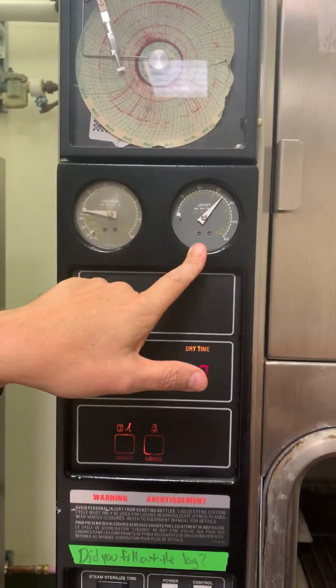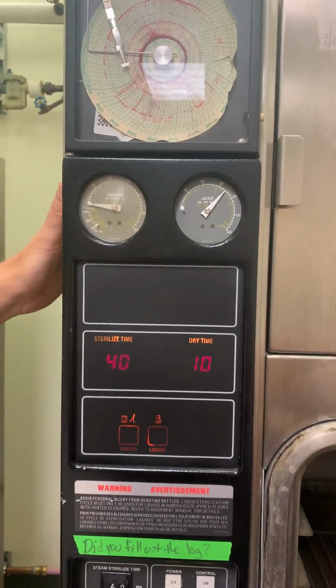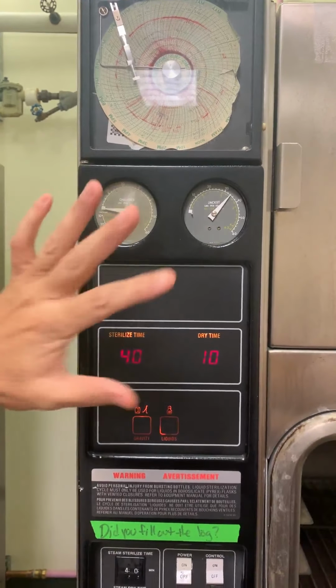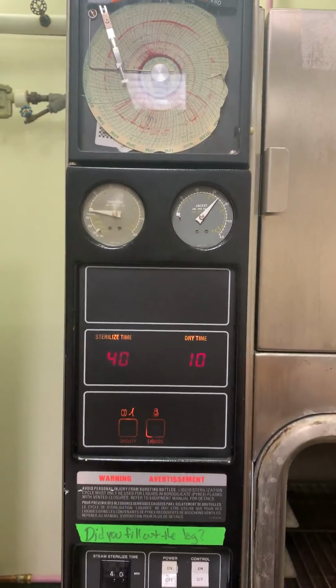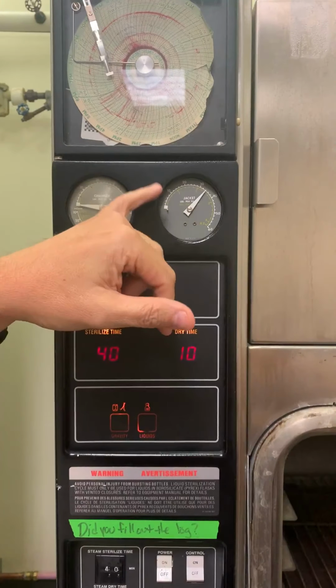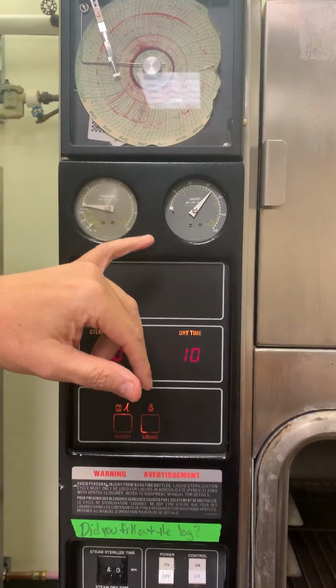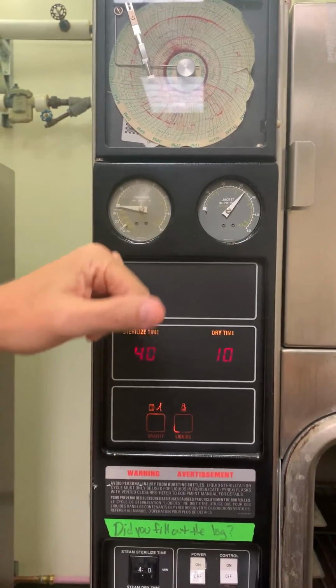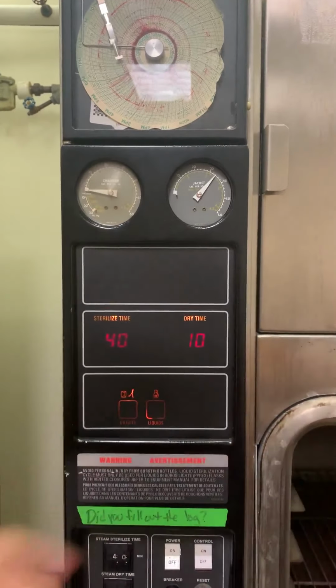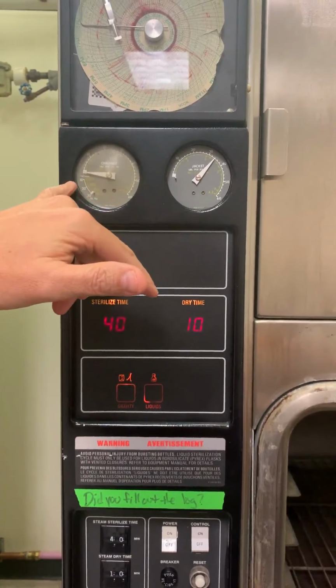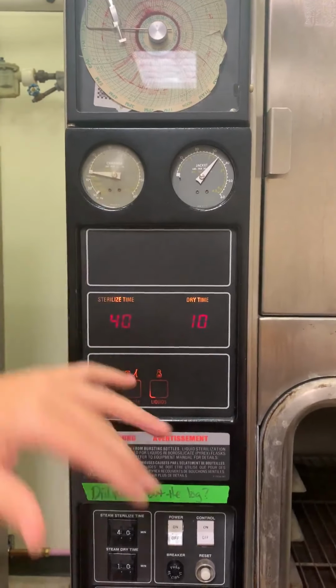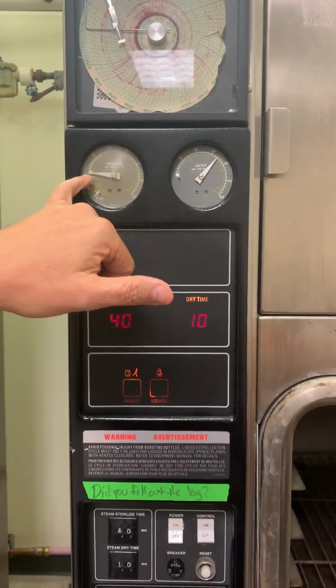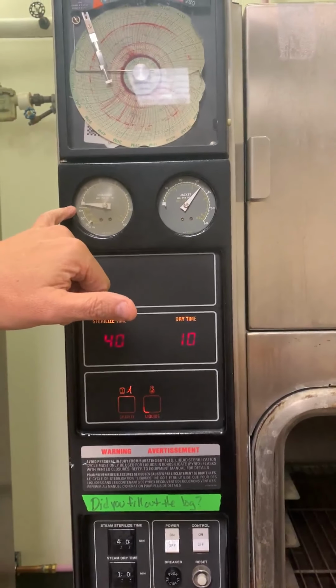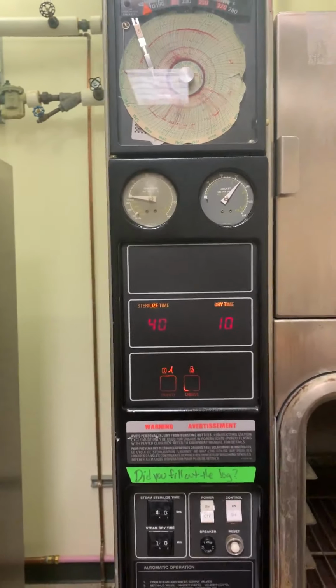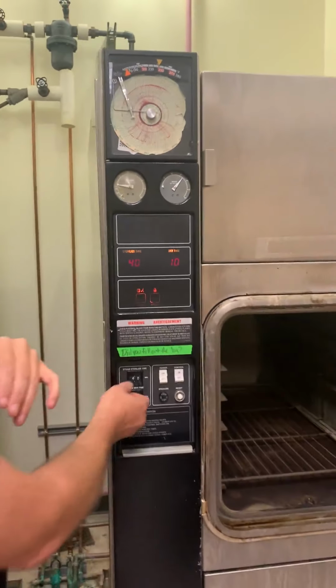We have 2 gauges on this machine. This is our jacket pressure. Jacket is where the stored pressurized steam is that's going to fill the chamber. It should always be above 25, 30 PSI and ready to go. You should never have to worry about this. This is the chamber pressure. Of course, the chamber is open, so it's not pressurized right now. But when you come back to open this, if the cycle's done, we want to be sure that the pressure is in that safe zone in the white right there.